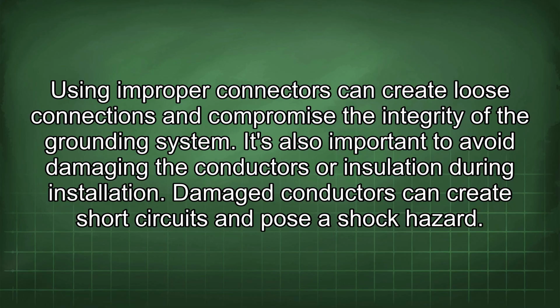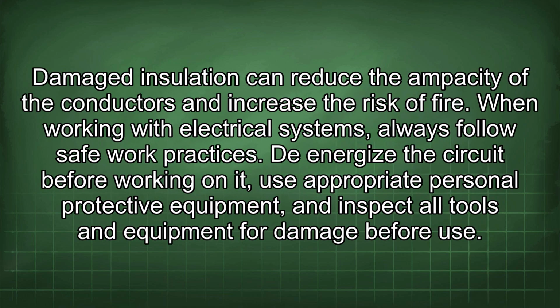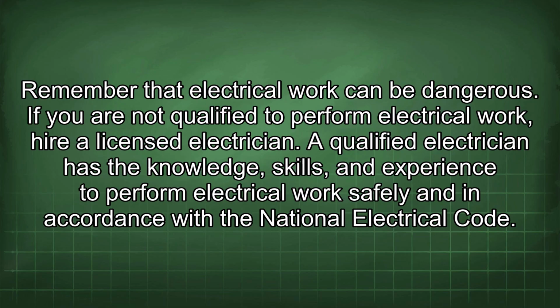It's also important to avoid damaging the conductors or insulation during installation. Damaged conductors can create short circuits and pose a shock hazard. Damaged insulation can reduce the ampacity of the conductors and increase the risk of fire. When working with electrical systems, always follow safe work practices. De-energize the circuit before working on it, use appropriate personal protective equipment, and inspect all tools and equipment for damage before use. Remember that electrical work can be dangerous.